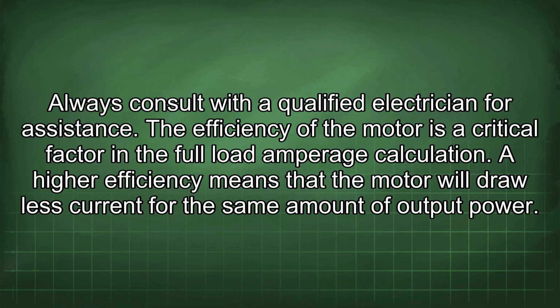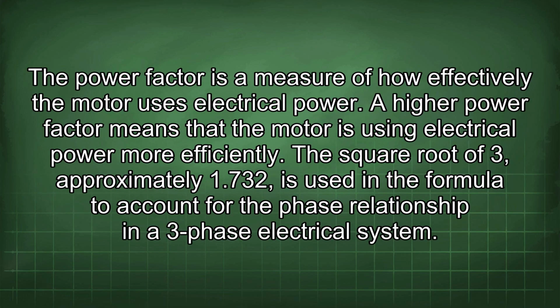The efficiency of the motor is a critical factor in the full load amperage calculation. A higher efficiency means that the motor will draw less current for the same amount of output power. The power factor is a measure of how effectively the motor uses electrical power. A higher power factor means that the motor is using electrical power more efficiently. The square root of 3, approximately 1.732, is used in the formula to account for the phase relationship in a three-phase electrical system.